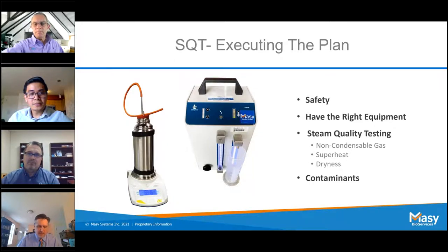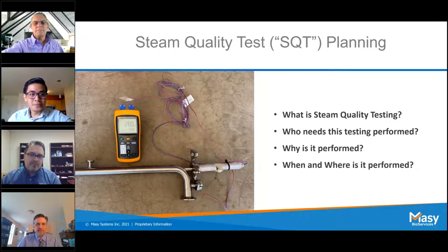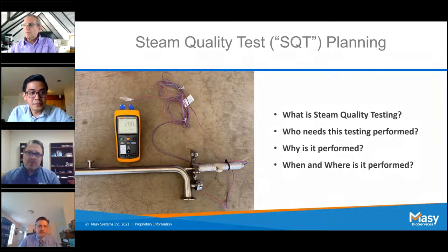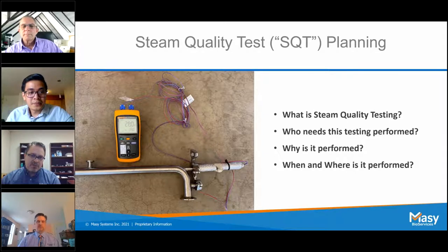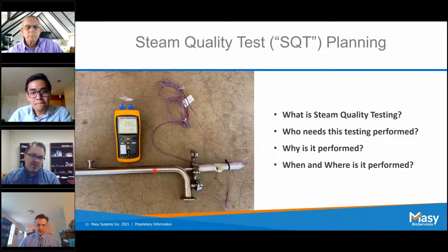Thank you. And Sylvan, what equipment do we need? Thanks, John. Are we able to back up to the earlier slide? Yeah, that'd be great. That way, not only the equipment, but maybe a little bit of the how as well, how things are done. Certainly. So the equipment we use, some of it is pictured right here, and I'll describe what you're looking at. That metal pipe near the bottom is a spool piece that we attach, supplied with sanitary fittings. When we locate the steam supply line, we connect that test pipe onto the steam supply, and there are a couple of additional connection points provided. We utilize those to extract steam from the system.